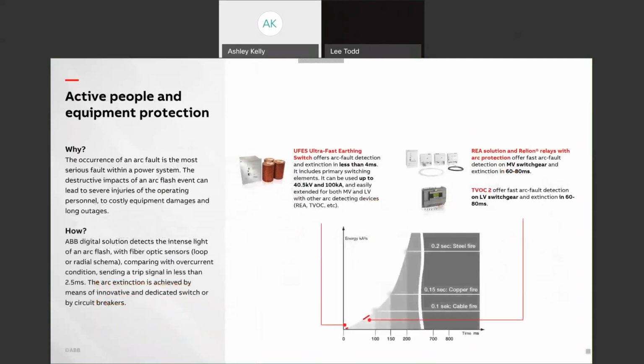So, why should you look to do this now? The answer's simple. Arc faults are the most serious fault within your power system. The cost to life and equipment and outages are real. Our active solutions can extinguish an arc fault in less than 4 milliseconds in the application of the ultra fast acting earth switch, and typically between 60 to 80 milliseconds using an arc protection Relion relay, obviously subject to the switching and tripping time of your breakers.